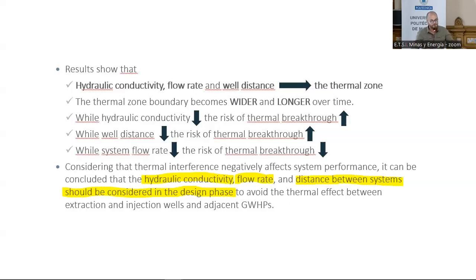I'm always combining both of them. Considering that thermal interference negatively affects system performance, it can be concluded that hydraulic conductivity, flow rate, and the distance between systems should be considered in the design phase. If you want to create a perfect system that works for 50, 60, or 100 years, you have to take into consideration the hydraulic conductivity, flow rate, and well distance effects.